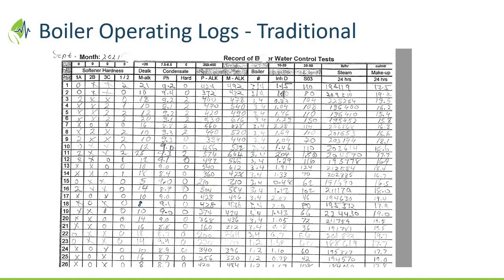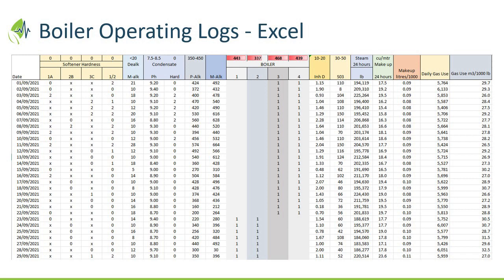Now you can trend it. Now you can look at the anomalies. Over on the right-hand side, because Julian was good enough to dig up the interval gas data, we added to that log how much gas we use every day. Now we've got something powerful. We know how much steam we produce. We know how much gas we use. We know on the right side there how much makeup water we used in 24 hours. Now you're turning this into a diagnostic analytical tool that you can use to maximize the efficiency of your plant.